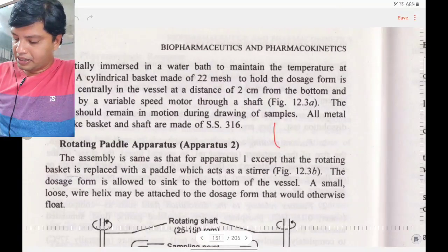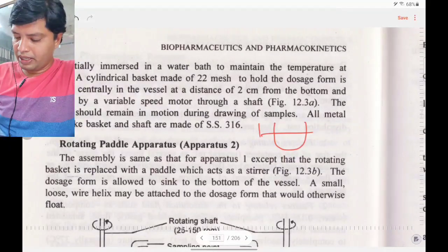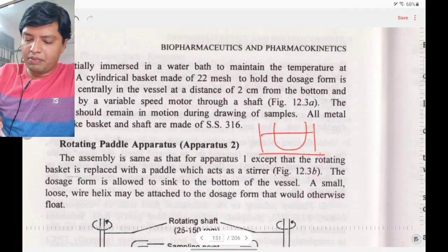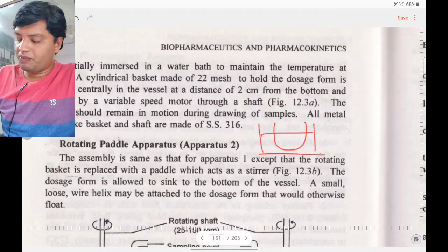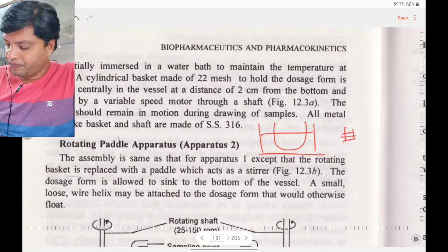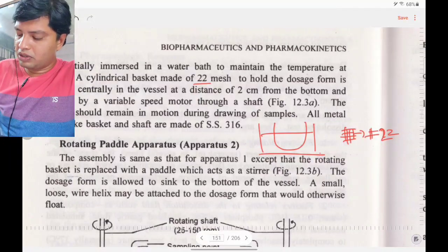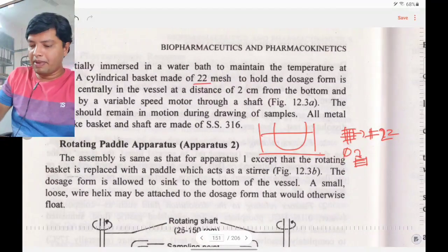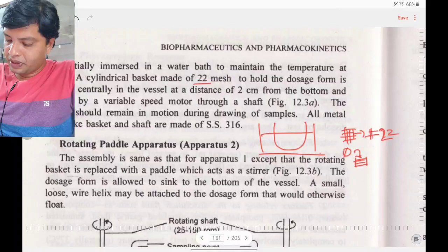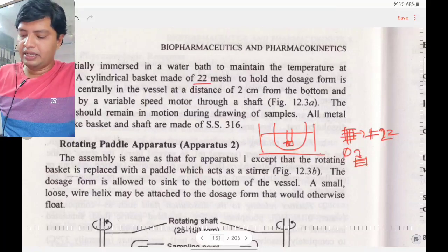The water bath is maintained at body temperature, 37°C. A cylindrical basket made of 22-mesh material holds the dosage form. The basket is located centrally in the vessel at a distance of two centimeters from the bottom and is rotated by a variable speed motor.